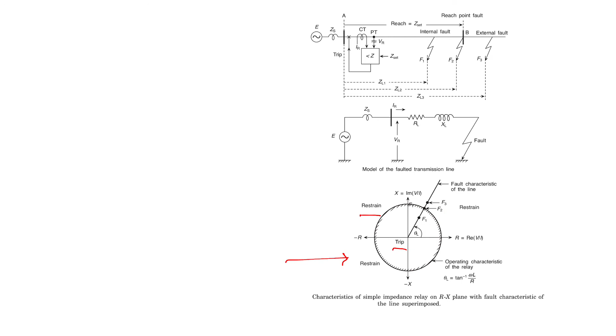Also, most of the faults involve arcing. The arc is resistive in nature. The arc resistance is a function of the spark over distance s, the wind velocity u and time t, and the current I in amperes. We discussed in the first chapter the Warrington formula for the arc resistance, which is given by R arc equals 8750 (S plus 3 U T) divided by I raised to the power 1.4. In this case, S is the spark over distance in feet, U is the wind velocity, T is the time in seconds, and I is the current in amperes.